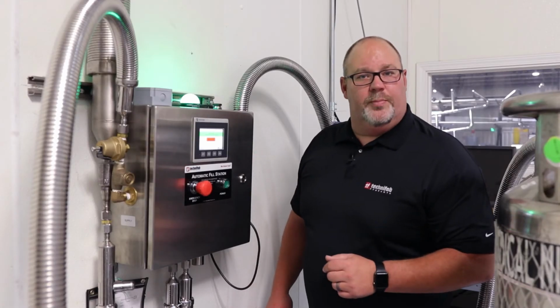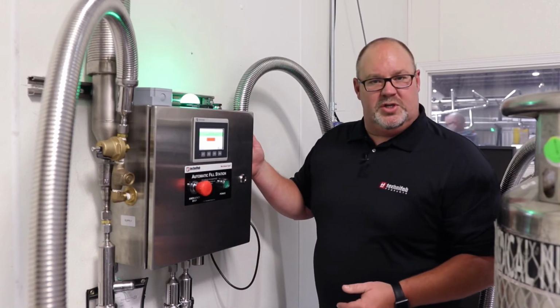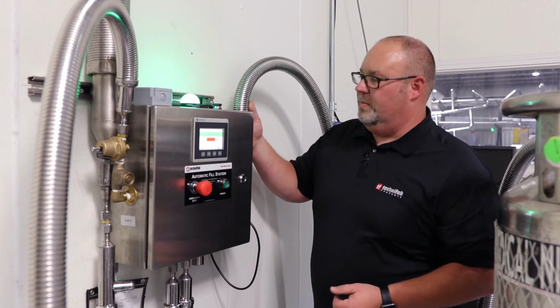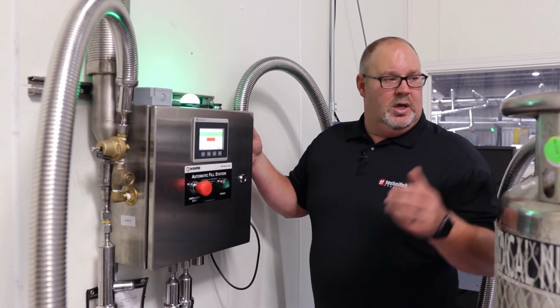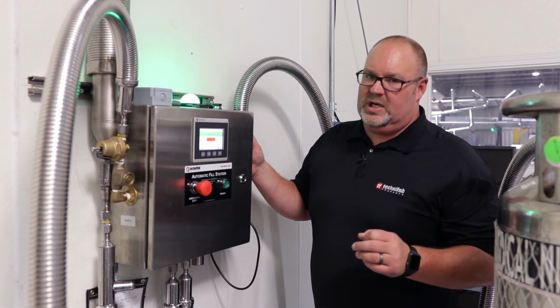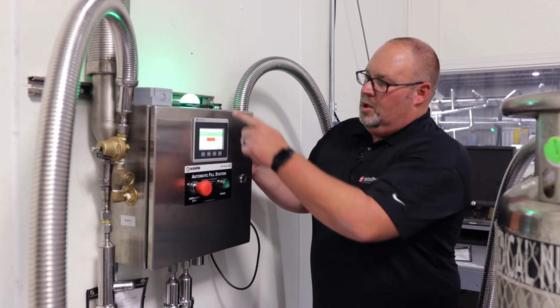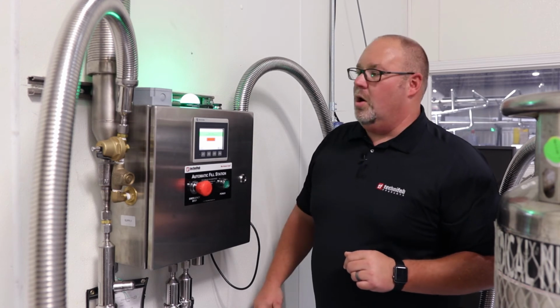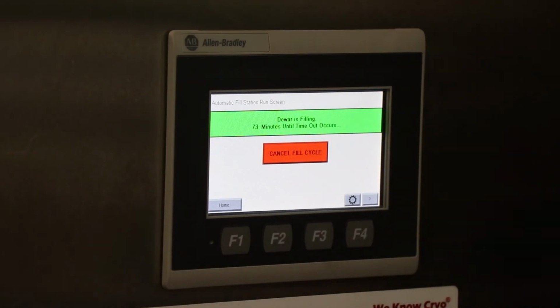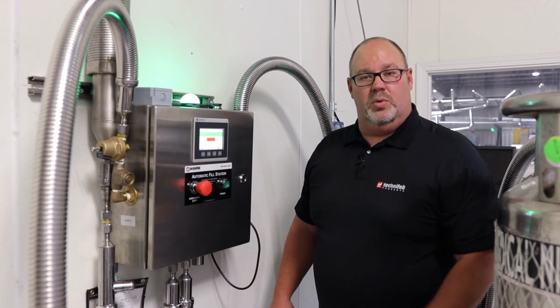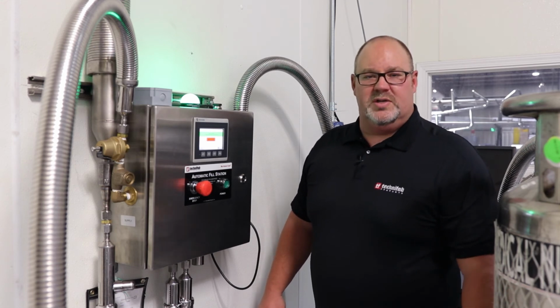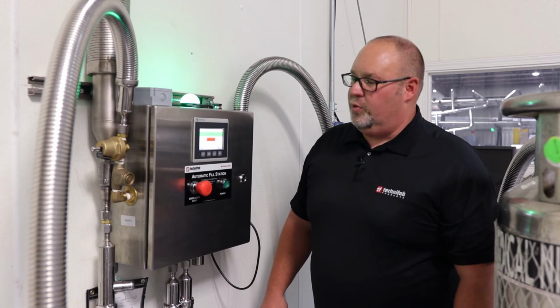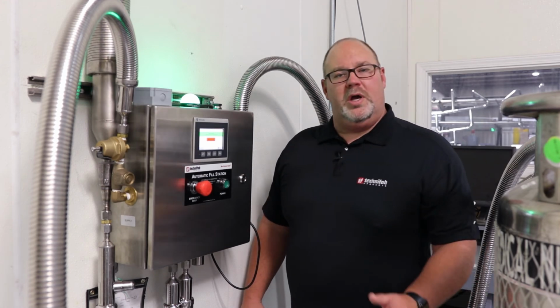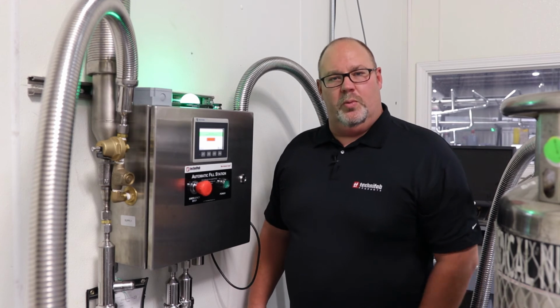So we've hit the button to start the process. We have a safety feature where there has to be a vent valve hooked up here to make sure that you're not just venting to atmosphere. It also allows a slight touch of back pressure on the system as well. The light turned green for us to indicate that we are in the filling cycle, and you'll see a green banner across the top which matches your light, and it also has your minutes countdown timer from when it will fail closed if the filling process is not completed. We'll come back once this dewar is finished filling, and we will complete the process.